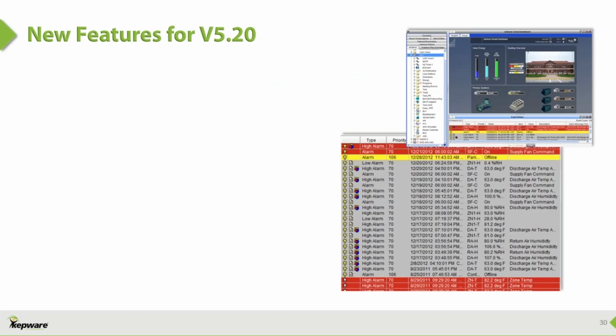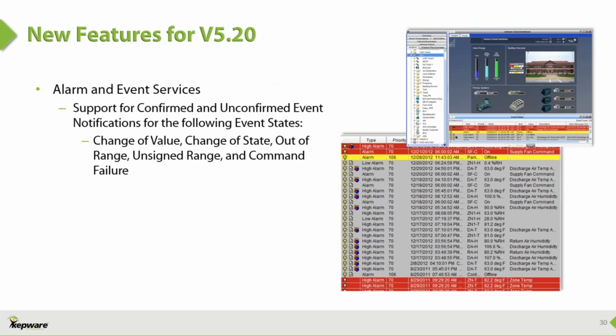In terms of alarm and event services, we now support confirmed and unconfirmed event notifications for the following event states: change of value, change of state, out of range, unsigned range, command failure. Unlike polling, the values are only delivered when they alarm. This reduces network traffic. Notifications are a different service than what you may be familiar with in terms of change of value or COV. These allow objects that don't support COV to notify those that are subscribed that a condition has actually occurred.